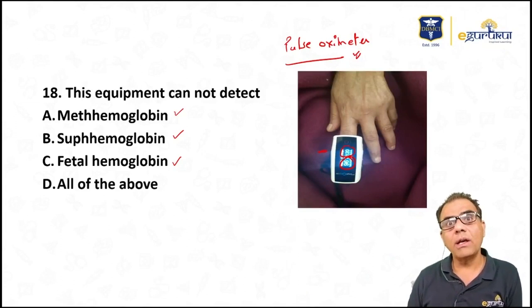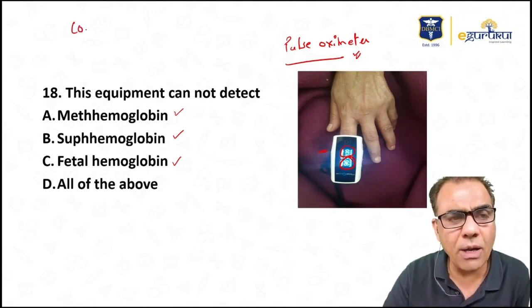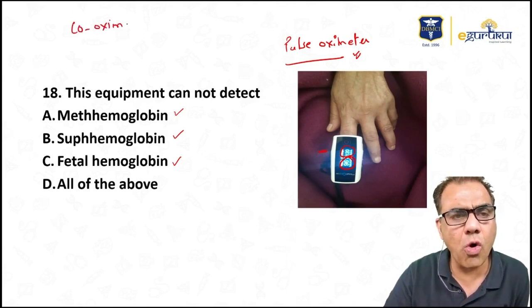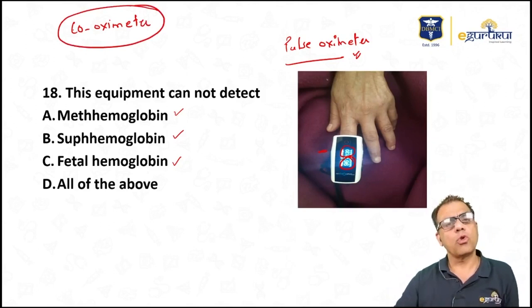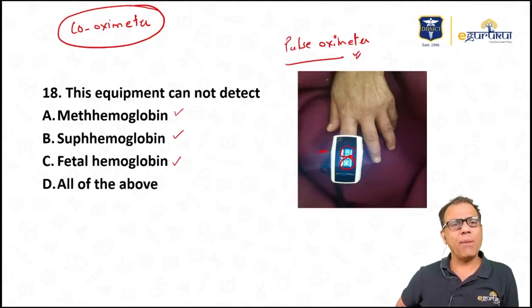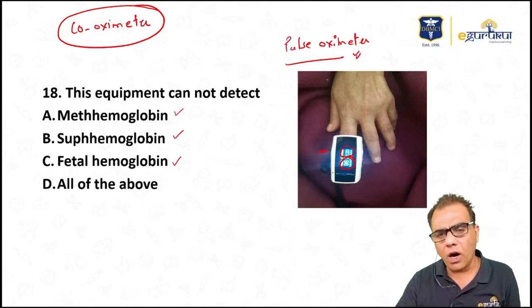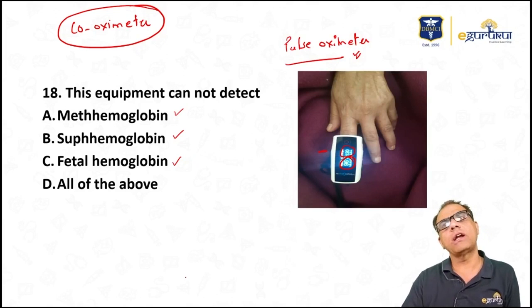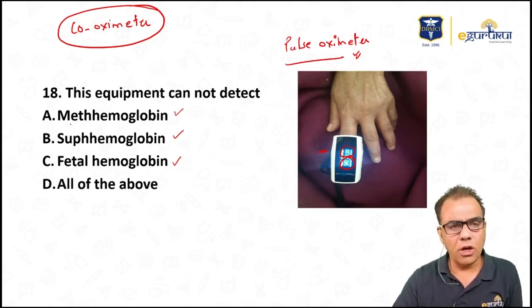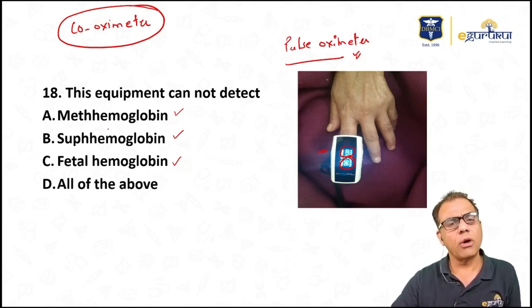So they are not accurate if there is a presence of abnormal hemoglobin. To detect abnormal hemoglobins, we have to use co-oximeters. Co-oximeters are a special kind of oximeter which can detect abnormal hemoglobin, while our normal pulse oximeters cannot detect abnormal hemoglobin.